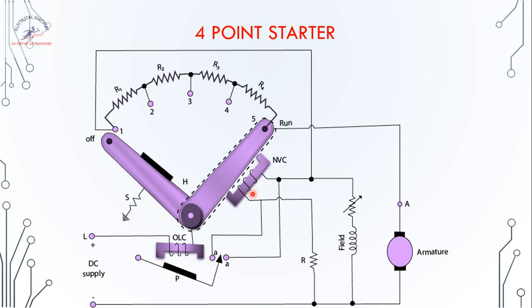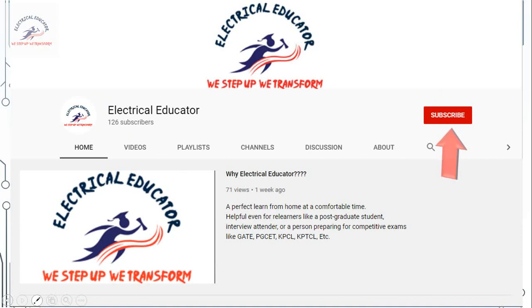The naming convention: a three-point starter has three connection points — Line, Field, and Armature. A four-point starter adds a separate NVC connection, giving four points: Line, NVC, Field, and Armature. All other features — the resistor banks, OLC, NVC working — are identical. These starters do not help in speed control; they only limit the starting current to protect the armature windings from burning out. That's all for today — please subscribe and hit the bell icon for instant notifications when new videos are released.